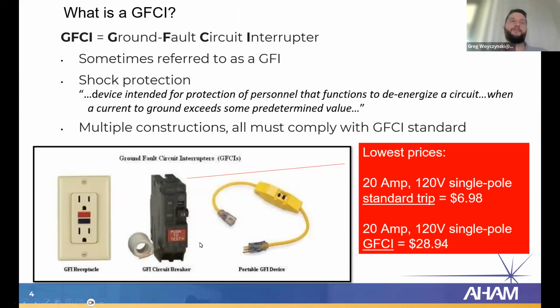So what is a GFCI? A GFCI is a ground fault circuit interrupter. It's sometimes referred to as a GFI. A GFCI and a GFI are the exact same thing, just a different name. And their intent is to provide shock protection. So they function to de-energize a circuit when current to ground exceeds some predetermined value. And we'll get into exactly what that means on the next couple slides.